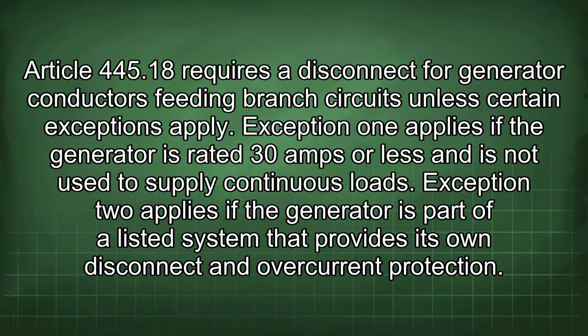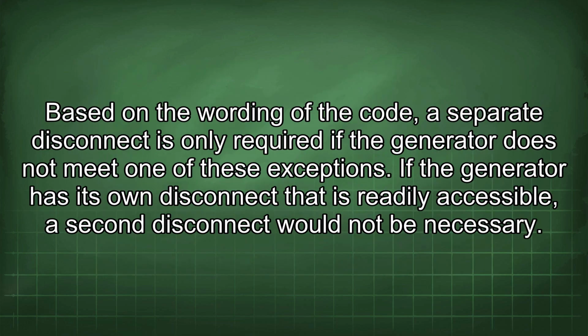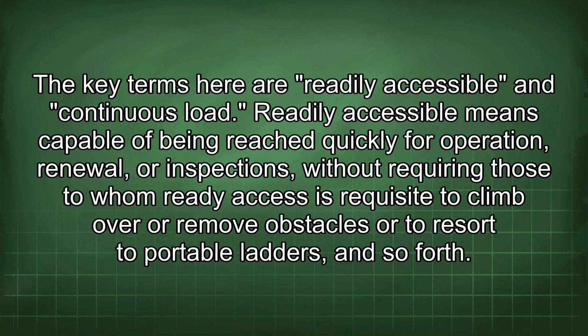445.18 requires a disconnect for generator conductors feeding branch circuits unless certain exceptions apply. Exception 1 applies if the generator is rated 30 amps or less and is not used to supply continuous loads. Exception 2 applies if the generator is part of a listed system that provides its own disconnect and overcurrent protection. Based on the wording of the code, a separate disconnect is only required if the generator does not meet one of these exceptions. If the generator has its own disconnect that is readily accessible, a second disconnect would not be necessary. The key terms here are readily accessible and continuous load.